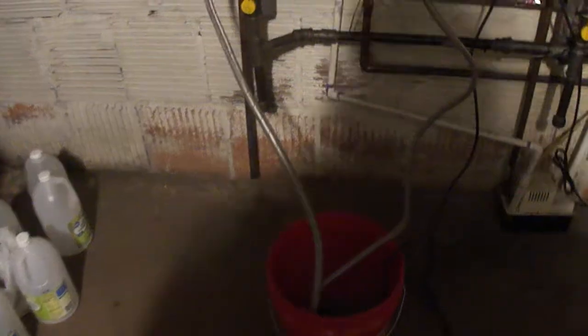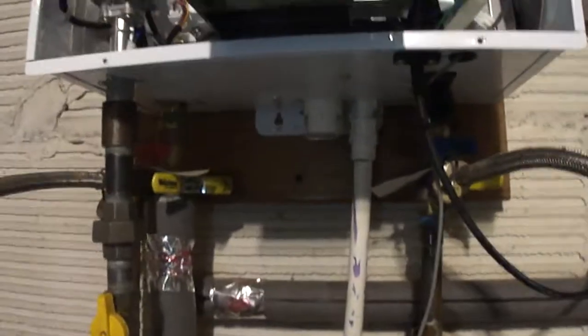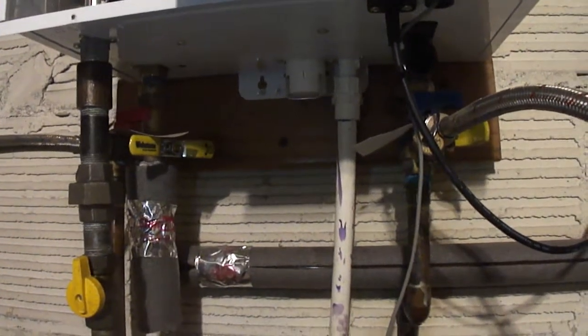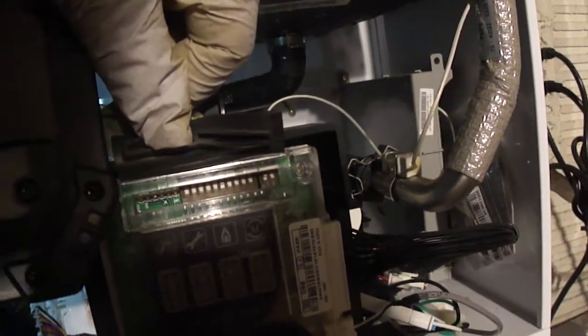Once you have the pump connected, make sure you have the valves properly open and properly closed. Make sure your incoming water and outgoing water valves are shut off, and then, let's say on the pump side, you just turn it on, and make sure you turn the other one on also, so the pump can circulate throughout the machine. Also, before you forget, behind this unit here, there are dip switches. On some of these models, these dip switches enable the pump to run through the machine. If you don't set the dip switches, it's not going to work.